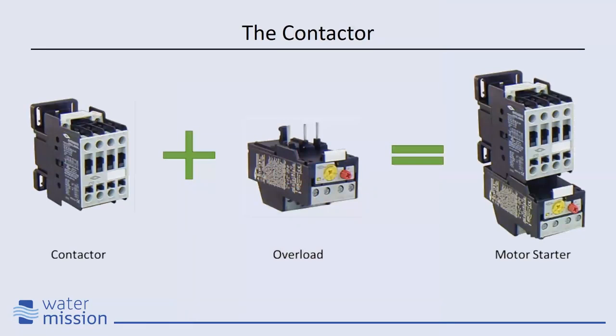So I mentioned having a contactor with an overload protection, an OCP, Overcurrent Protector. Those oftentimes are even bought together and they physically mate with each other. That, as a unit, is called a motor starter, okay? And you should always see those together.